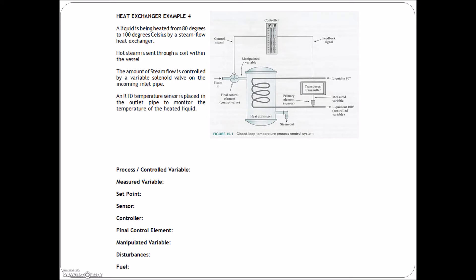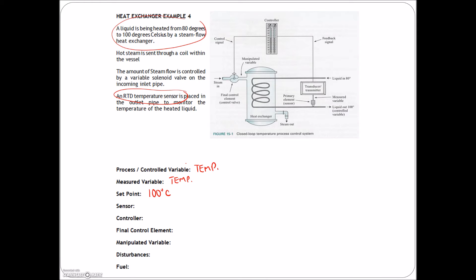Next example: a heat exchanger. Liquid is being heated from 80 to 100 degrees Celsius by a steam flow heat exchanger. Hot steam is sent through a coil within the vessel, the amount of steam flow is controlled by a variable solenoid valve on the incoming inlet pipe, and an RTD temperature sensor is placed in the outlet pipe to monitor the temperature of the heated liquid. What we're trying to control is temperature. What we're measuring — we're using an RTD temperature sensor, so we're measuring temperature. The set point is 100 degrees Celsius.